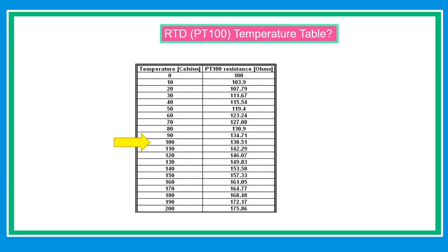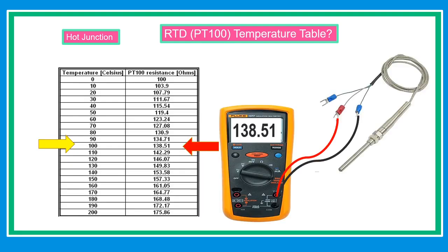An RTD resistance can be converted into temperature that gives values of temperatures for any given resistance. The table below shows temperature versus resistance in degrees Celsius. If we are going to look at the yellow arrow 100 degrees Celsius and the reading of our multimeter, if we are going to calibrate, it should be 138.51 ohms.